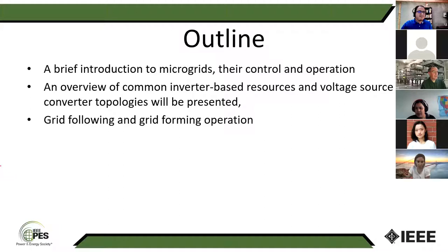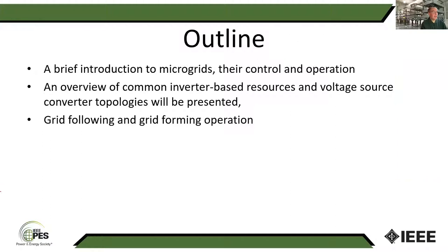and their controls. And then one of the things that also comes up with inverter-based resources is how you control it. Most things that use inverters right now are controlled in what's called a grid following mode, which means that they try to follow the power system frequency and phase angle and basically maintain a constant power or something like that. But if you have an isolated system, then you need something that's going to act as the frequency master for the system. And so that's what I refer to as grid forming.